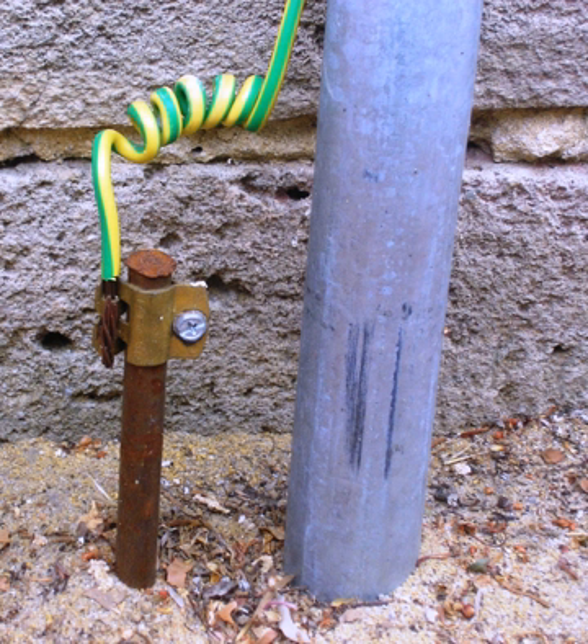High-resistance grounding (HRG) systems use an NGR to limit the fault current to 25A or less. They have a continuous rating, and are designed to operate with a single ground fault. This means that the system will not immediately trip on the first ground fault. If a second ground fault occurs, a ground fault protection relay must trip the breaker to protect the circuit.